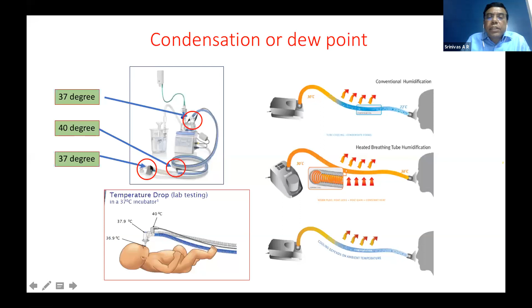So again, why we should not be using centralized medical gases? The temperature can be generally -20 to +20 degrees centigrade, which is much lower. Babies require 37 degrees centigrade air. The relative humidity is only 2% in medical gases. The baby's lung requires 100%. And medical gas absolute humidity is only 0.3 milligrams per liter, whereas the baby requires 44 milligrams per liter to attain 100% relative humidity.